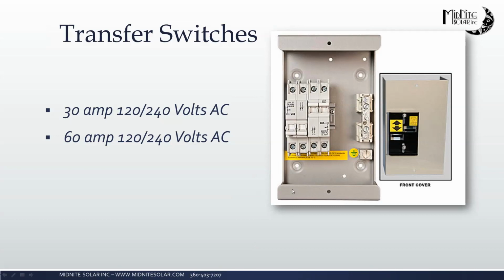You want to talk about transfer switches as well? Happily. The transfer switch, just as it says, it's made to transfer a load from a couple different inputs, or a couple different loads from a single source, if you will. A couple examples of that would be, let's say you've got a well pump and you've got a generator and an inverter, and you want to be able to run the well pump directly off the generator. Or let's say you've got an inverter and you're off grid and you have a couple different generators. You want to be able to select between generator A and generator B.